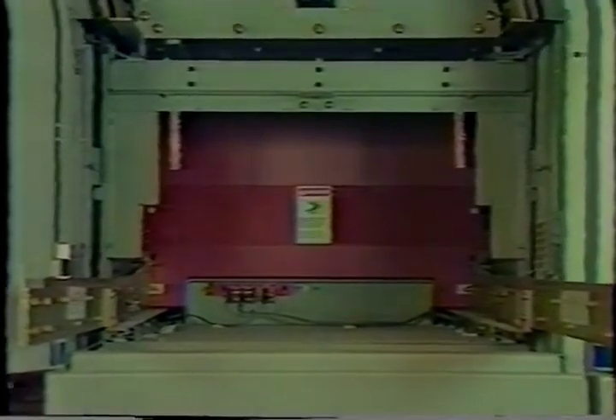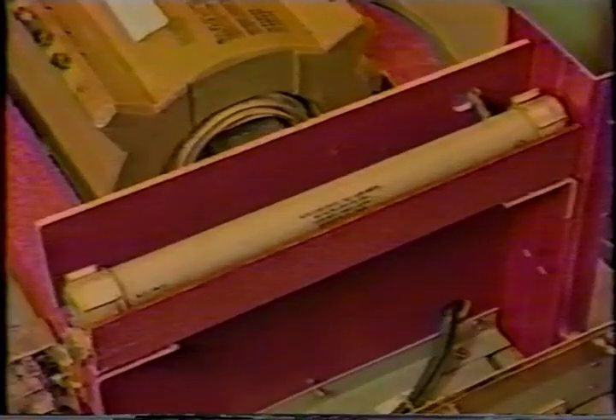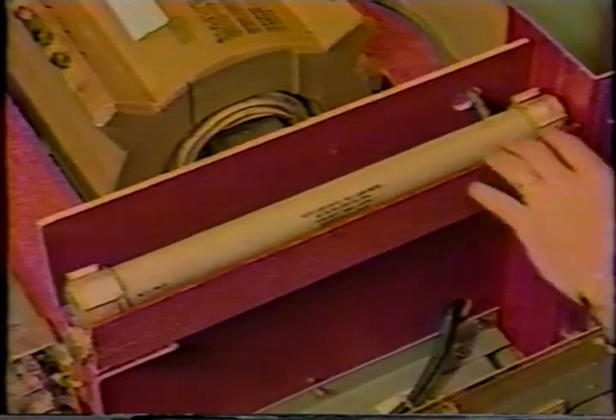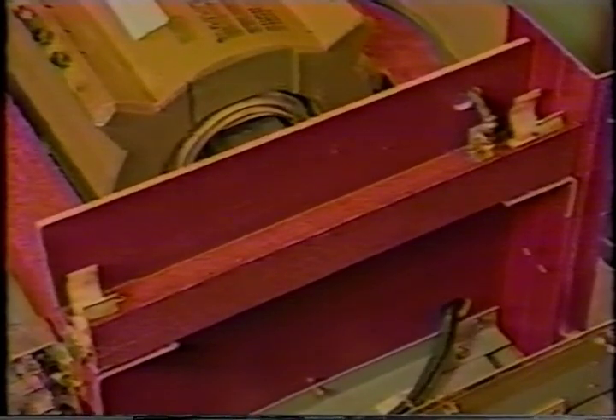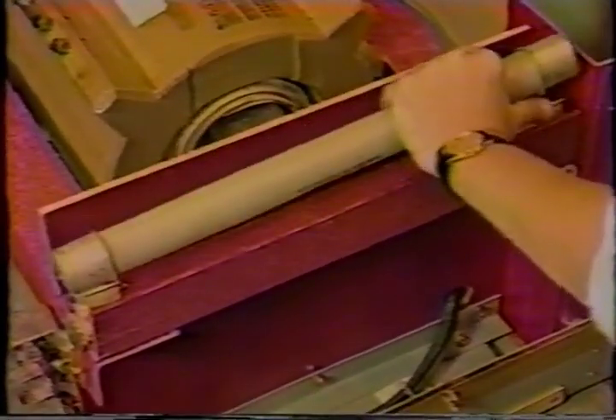Do not attempt to remove the back covers, the disconnecting assemblies, or shutters unless the high voltage circuit to the compartment is de-energized and precautions have been made to prevent re-energization. Failure to de-energize the circuit and take precautions to prevent re-energizing could result in bodily injury or electrocution. When energized, these circuits carry lethally high voltages. With the exception of apparatus such as current transformers and rear-mounted heaters, control equipment and wiring is generally accessible without exposing high voltage parts.